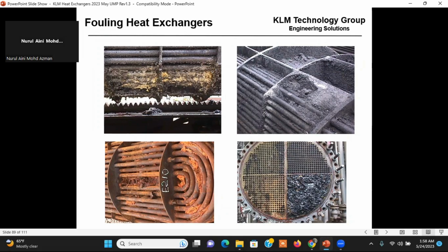basically, this is the bottom half, the bottom 20% of this heat exchanger is fouled. Okay, that's a pretty ugly picture there. These pockets right here are all full of fouling materials. You're not going to get any heat transfer here. This is polybutadiene fouling, and this is cooling tower fill, where the cooling tower kind of broke apart and plugged up the cooling water side of a heat exchanger.